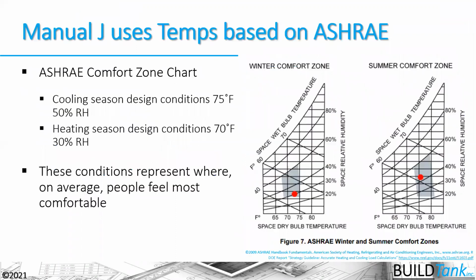And these numbers are coming from ASHRAE, who has developed this comfort zone chart, and have determined that those design conditions in cooling season and heating season are the ideal design conditions to create comfort in the interior of that house, regardless of what the temperature is outside the house. So that's why these are codified indoor design temperatures for heating and cooling seasons there.